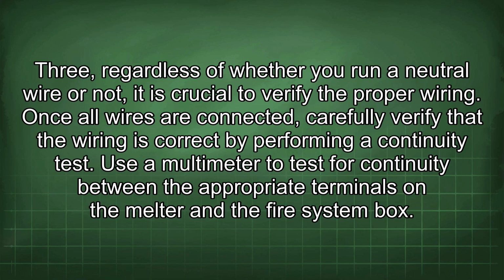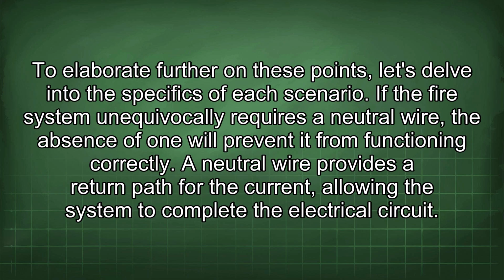3. Regardless of whether you run a neutral wire or not, it is crucial to verify the proper wiring. Once all wires are connected, carefully verify that the wiring is correct by performing a continuity test. Use a multimeter to test for continuity between the appropriate terminals on the melter and the fire system box. To elaborate further on these points, let's delve into the specifics of each scenario.